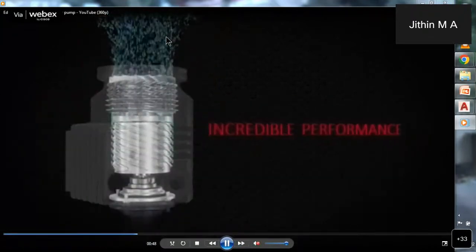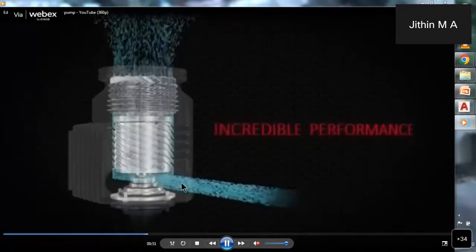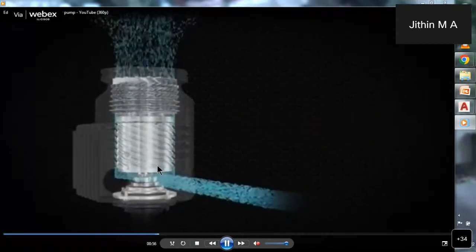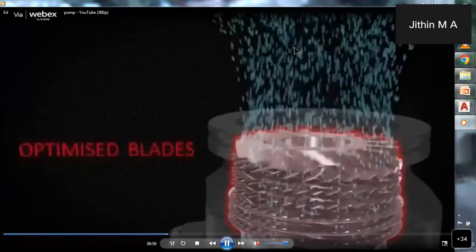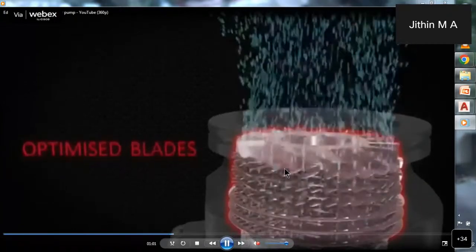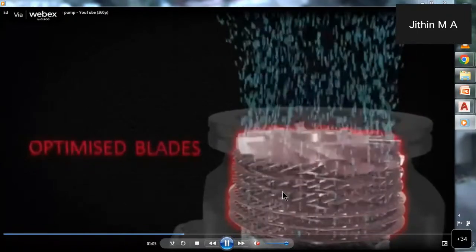So this is the inlet of air molecules and it is going out from the exhaust. The rotary pump will be connected to this exhaust as a backing pump to remove the gas molecules coming to the rear side of the turbo pump. Okay, so this is how the turbo pump works. These are the rotors and the stator, which I can show you in the next video.